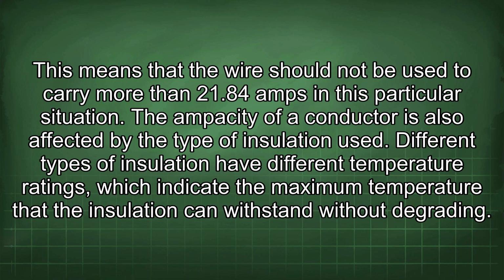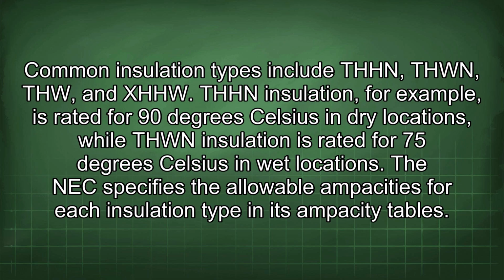The ampacity of a conductor is also affected by the type of insulation used. Different types of insulation have different temperature ratings, which indicate the maximum temperature that the insulation can withstand without degrading. Common insulation types include THHN, THWN, THW, and XHHW. THHN insulation, for example, is rated for 90 degrees Celsius in dry locations, while THWN insulation is rated for 75 degrees Celsius in wet locations. The NEC specifies the allowable ampacities for each insulation type in its ampacity tables.